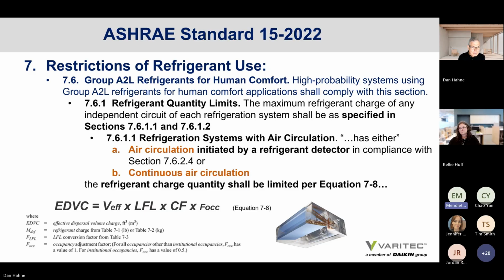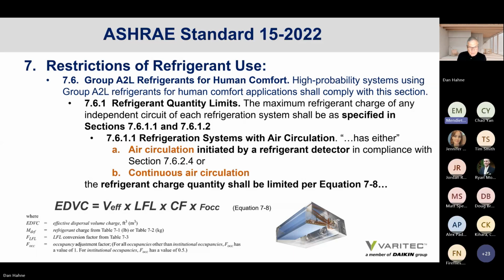Yeah, I guess it's the way you're looking at these equations, because Dan and I looked at these and I didn't realize that there's one for A1 and another one for A2, that they're different equations. As far as the EDVC, that's the amount of refrigerant you're allowed into the space, which is the same thing as the way you're defining RCL. One is saying there's a certain amount of refrigerant you're allowed into the space, and the other is saying here's the amount of refrigerant you are releasing into the space, which is MREL. So I believe we're talking about the same thing. It's just defined differently depending on whether you're looking at A2 or A1. It's still a refrigerant concentration limit if you're looking at it in terms of the quantity of refrigerant.